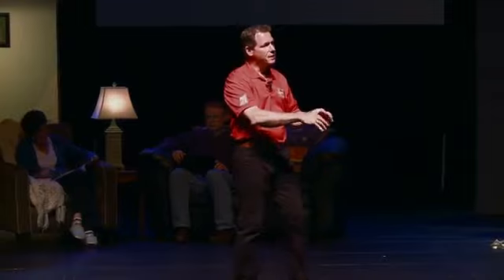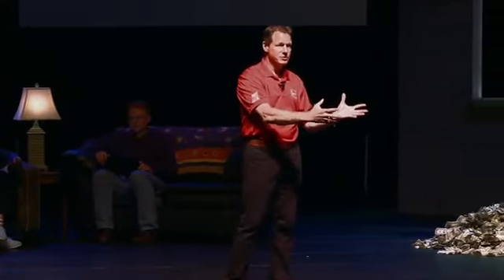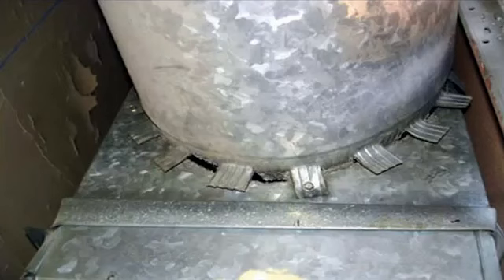The cold winter air freely entering the crawl space vents cools the ducts and the warm air in them, while the furnace makes 120-degree air and sends it through the duct system to the rooms we want to heat. This air may only be 95 degrees by the time it comes out of the heat registers in those rooms. Anyone can understand that a furnace will have to run longer to heat a room with 95-degree air than it would with 120-degree air. Then there are duct leaks.